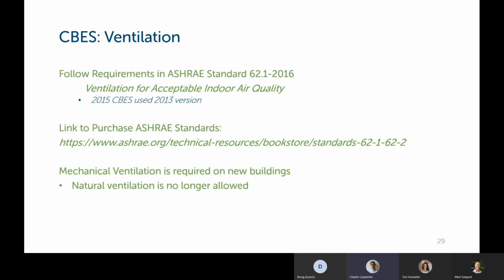The biggest change in ASHRAE 62.1 2016 versus the previous version is that mechanical ventilation is now required for all new commercial buildings. It does not have a provision for natural ventilation anymore. So that is one thing to keep in mind, is that mechanical ventilation will be required for all new buildings on the 2020 energy code. Next slide. Okay, that's an important change to note. Yep.